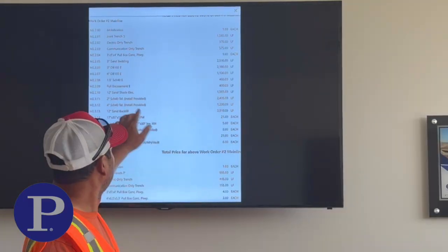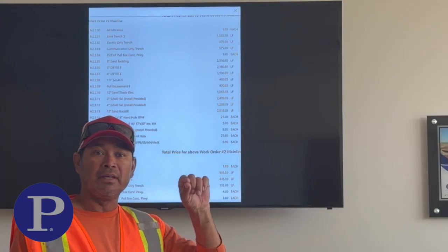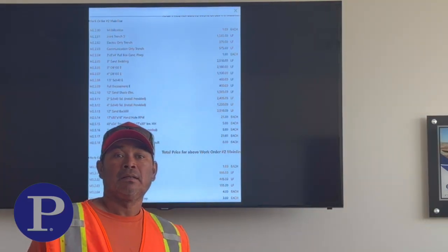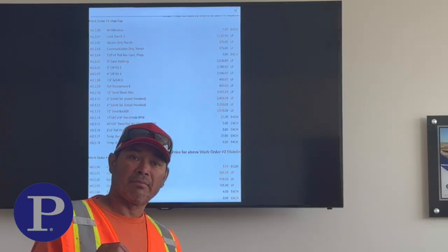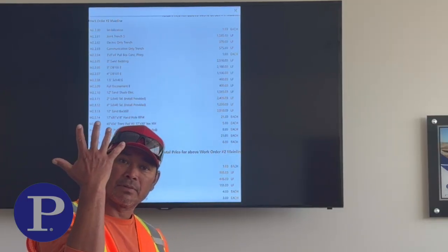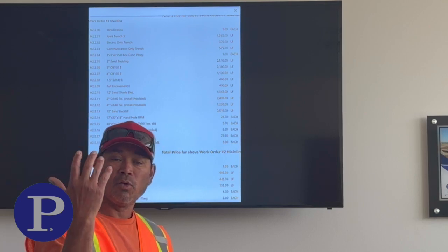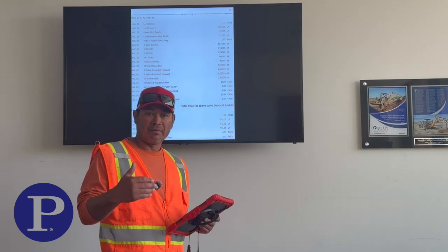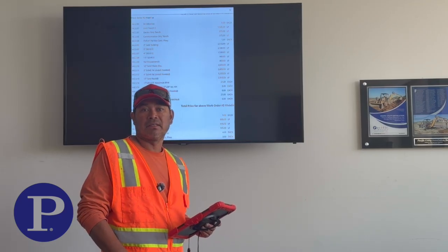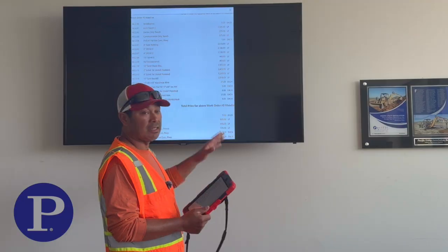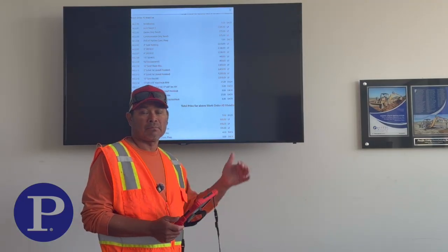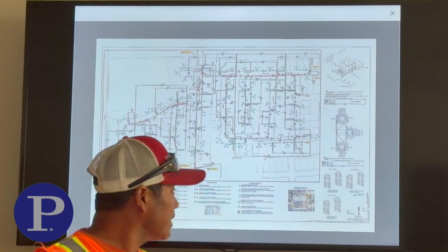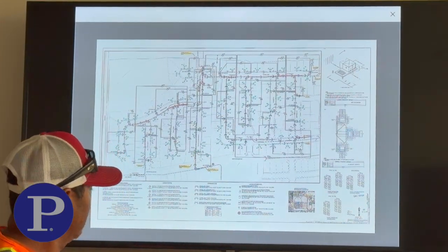I'm not gonna say right now, I haven't studied this specific why we need those 400 foot of encasement. It's gonna be in little sections because we probably have more than 5 pipes on a single family. If you have 4 or less in single family, you don't need it. But if you have 5 or more, you will need it. So just something to take into consideration because it's really high price when you put in concrete when you don't need it. So this is the system, the way IID designs.